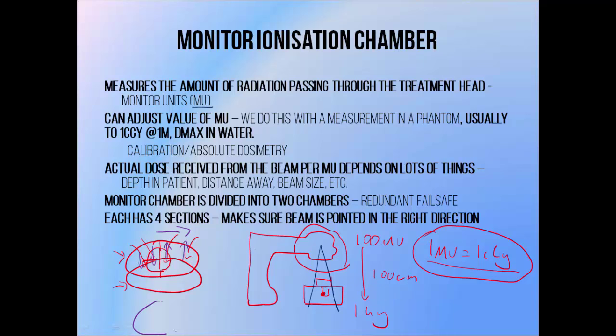The second chamber is divided up in a similar way but at a 90-degree angle to the first, so it's able to pick up changes in the beam in the other direction. If the signal in two regions goes up and the signal in the opposite two regions goes down, that means the beam has moved, and the machine is able to steer it back on course. So the monitor chamber makes sure the patient gets the right amount of radiation and makes sure that the beam is pointed in the right direction.